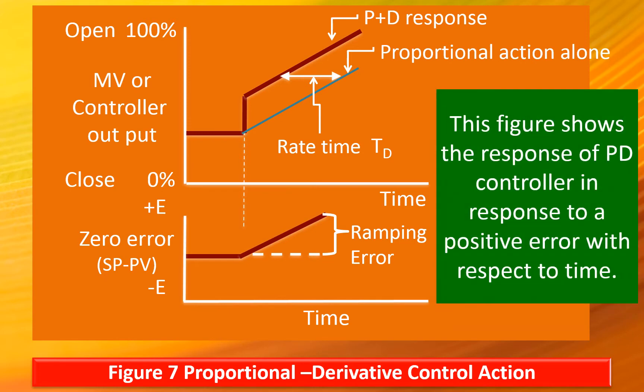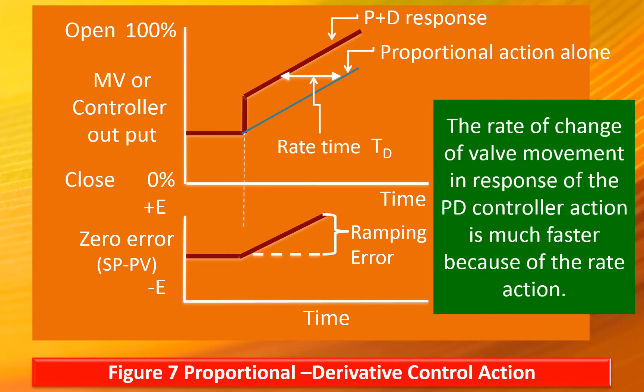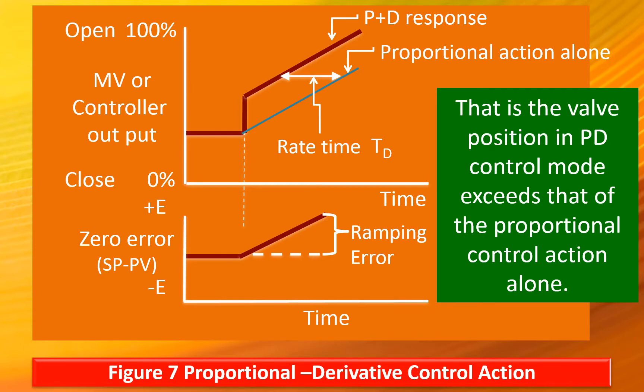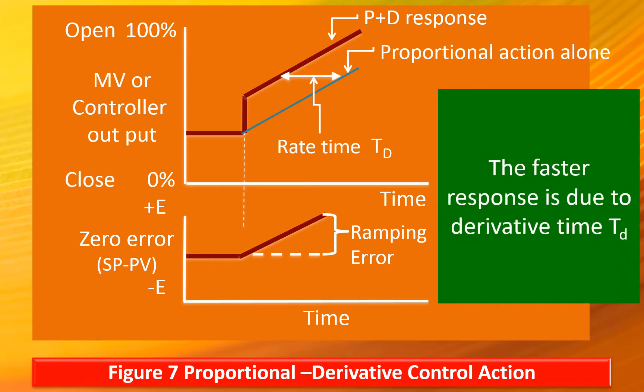This figure shows the response of a PD controller in response to a positive error with respect to time. Observe the proportional response alone — the rate of change of valve position of the control valve is slower. The rate of change of valve movement in the PD controller response is much faster because of the rate action. The valve position in PD control mode exceeds that of proportional control action alone, and it takes less time for the valve to ramp up in PD control mode. The faster response is due to the derivative time Td.